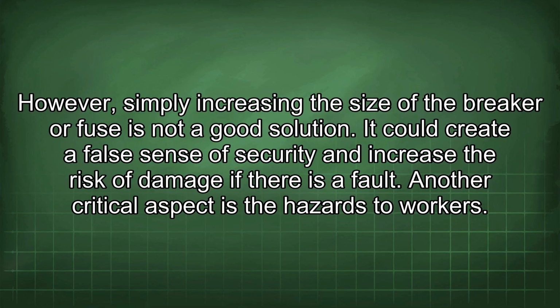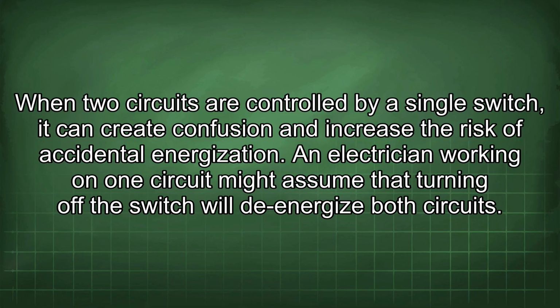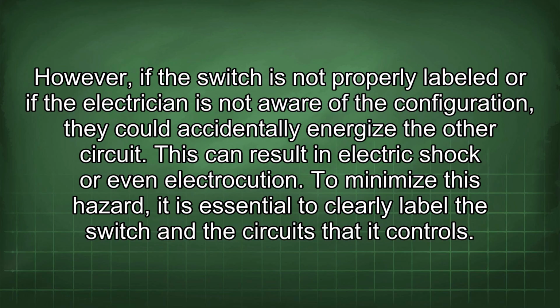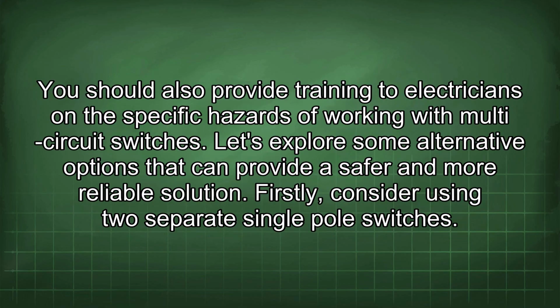Another critical aspect is the hazards to workers. When two circuits are controlled by a single switch, it can create confusion and increase the risk of accidental energization. An electrician working on one circuit might assume that turning off the switch will de-energize both circuits. However, if the switch is not properly labeled or if the electrician is not aware of the configuration, they could accidentally energize the other circuit. This can result in electric shock or even electrocution. To minimize this hazard, it is essential to clearly label the switch and the circuits that it controls. You should also provide training to electricians on the specific hazards of working with multi-circuit switches.